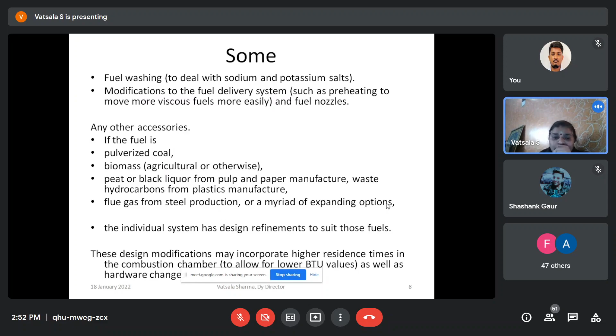The individual systems are designed with refinement to suit those fuels, because whatever product or residual is there may not be in a condition ready to use. So refinement is required in the boiler design, and also in the fuel design. The design modification may incorporate higher residence time in the combustion chamber and allow a lower BTU value, as well as hardware changes. So as per the requirement of the fuel, we sometimes make moderate modifications to design parameters as required.